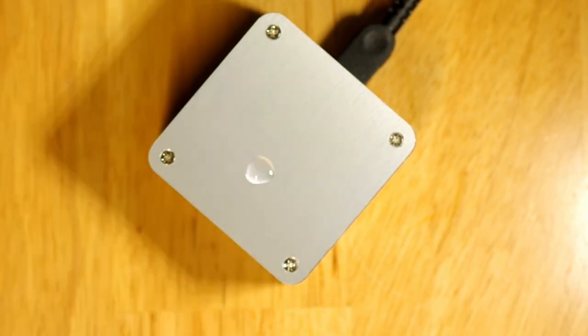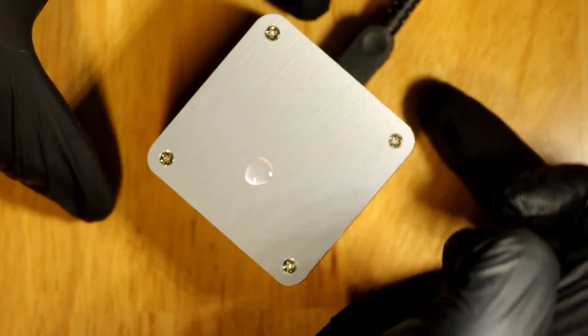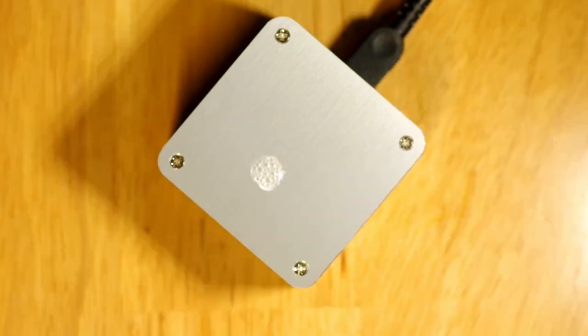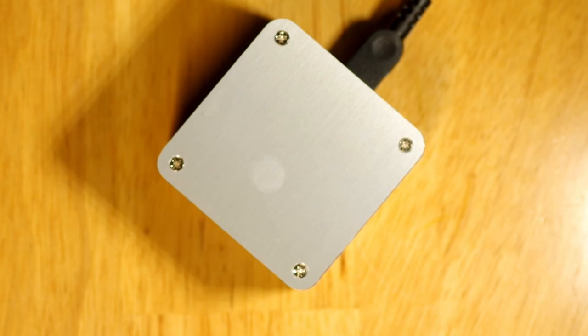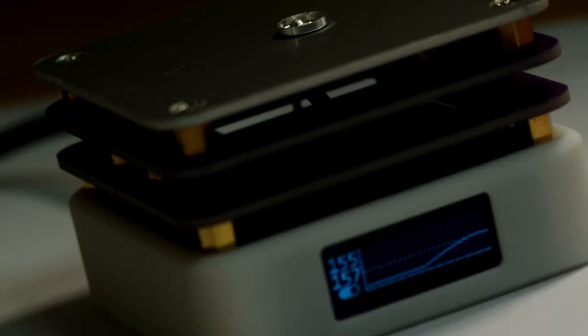Once this is accomplished, I got curious to see if the display temperature is the same as the actual temperature. And to test this, I used indium in an aluminum pan.